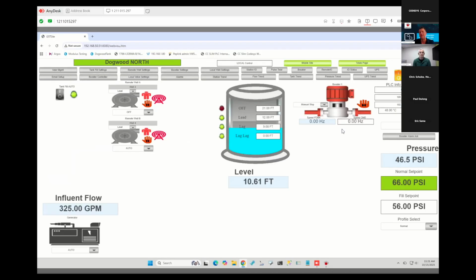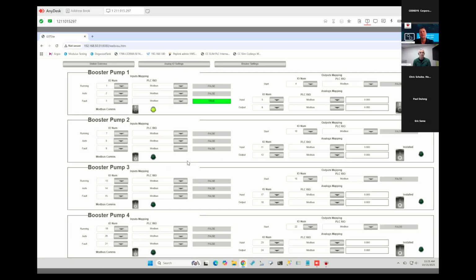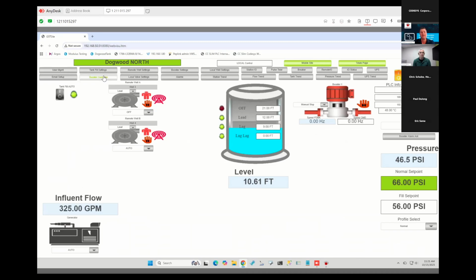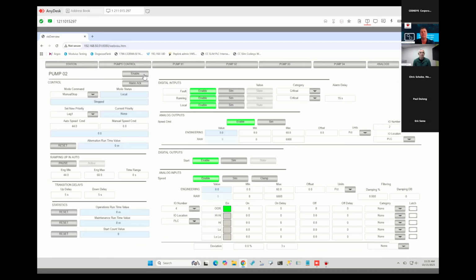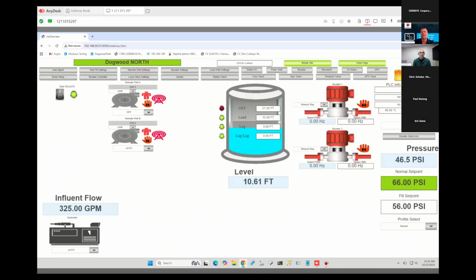The other nice feature here using the WebVisu is, so right now I've got 1 booster pump in this setting. So I'm going to go here and I'm going to turn on a second booster pump, and I'm going to make sure my pump controller knows it's enabled. And then once that's done, I now have a second booster pump right there on my visualization. So using the WebVisu, we're able to hide graphics. Everything is a template inside of here. Same with the fill cycle.